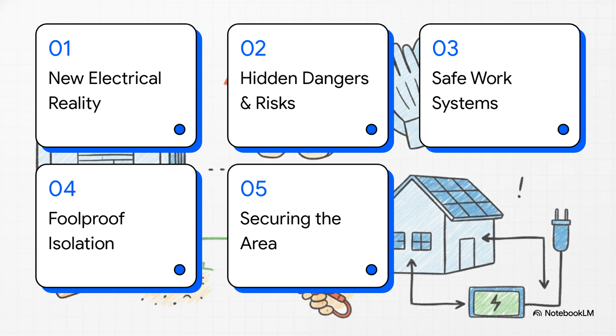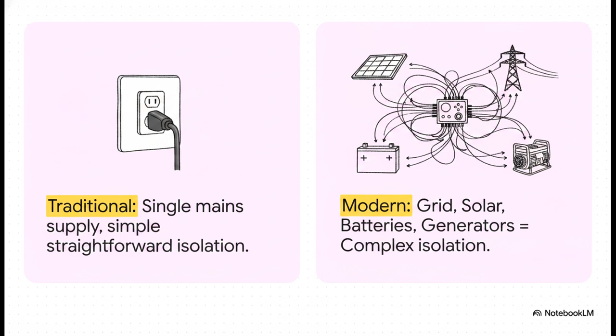Section 1: The new electrical reality, a changing grid. Thinking about the traditional versus the modern setup brilliantly illustrates exactly what we've moved away from. Back in the day, with a traditional setup, you had a single main supply. You throw one main switch, cut all the power, and boom, you get to work safely. But in a modern setup, you've got the grid plus solar PV plus battery storage and standby generators all tied together. Isolation is no longer just a single action, it's a complex, multi-layered procedure.